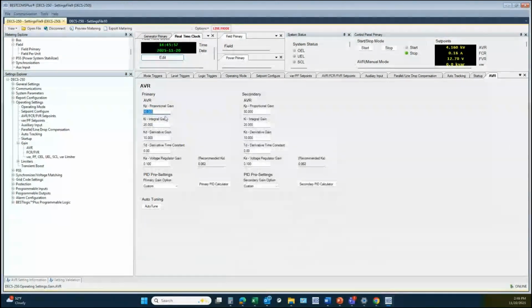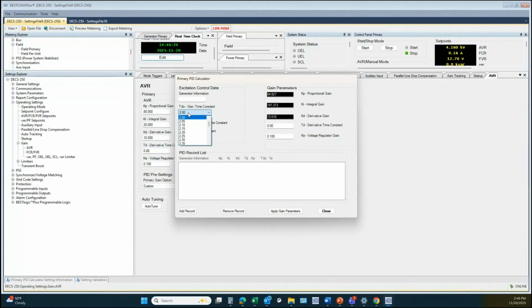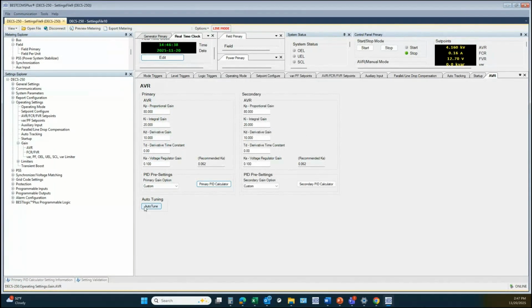Gains. So we have some default gains in here. I do not recommend using the default gains. There are custom gains if you know some basic time constants of your exciter and generator. You can select from a list, or you can use this PID calculator, which allows you to enter your generator time constant and your exciter time constant. And then once you do so, it will provide some recommended gain values. Or with these modern DECS products, you can actually use the auto tuning feature.